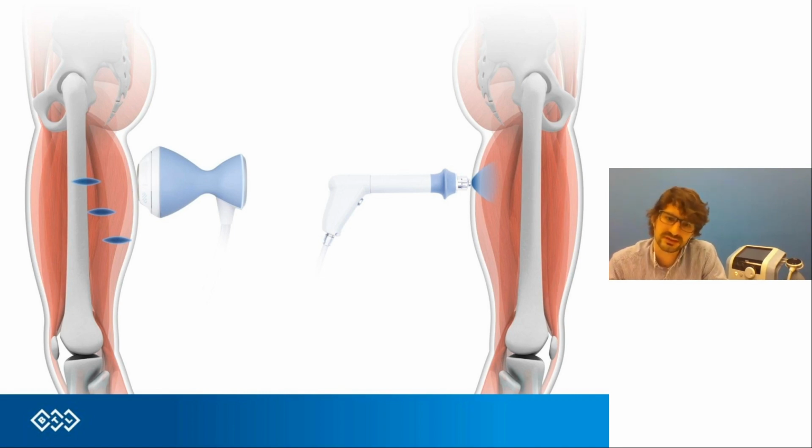But in general, radial shock waves are more superficial, whereas with the focus shock wave, it is possible to adjust the area that I want to treat. It is possible to adjust on the applicator and get inside the patient's body, or even treat the superficial area. But the biggest difference is that with the focus shockwave, you can choose which areas inside the body you want to treat. With the radial shockwave, it will be a little limited because you don't have the ability to change this.